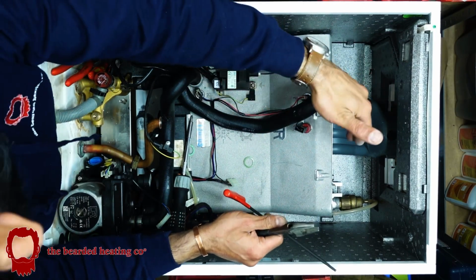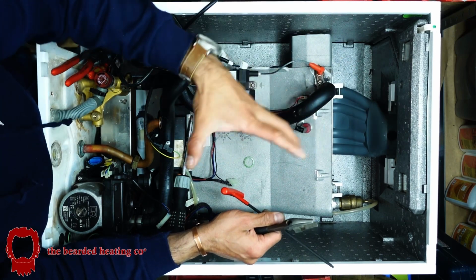So that's basically how you would end up servicing the Remeha Calenta. You would open up the burner door, get it out of the way, check the burner seal, and check the burner.